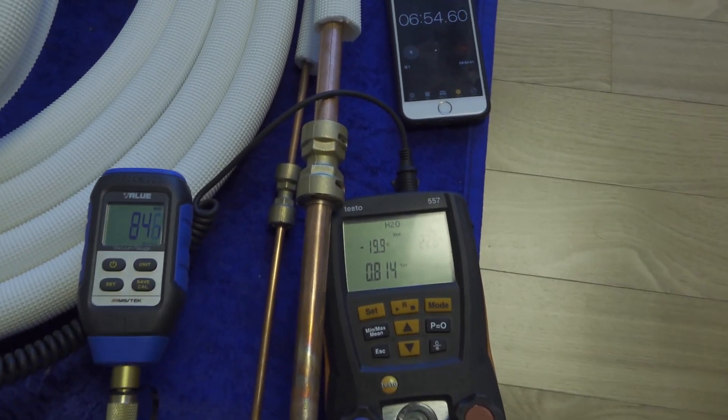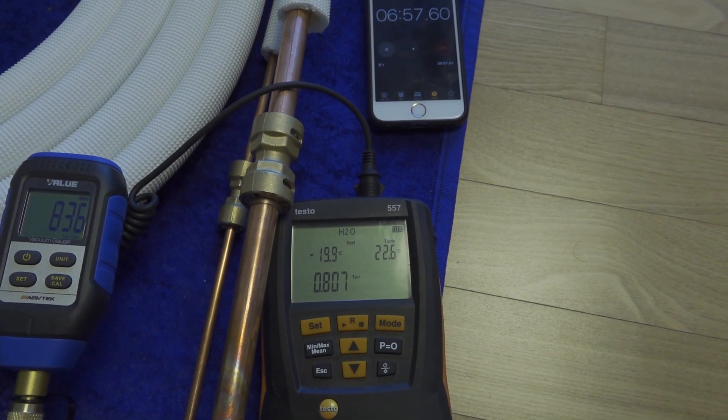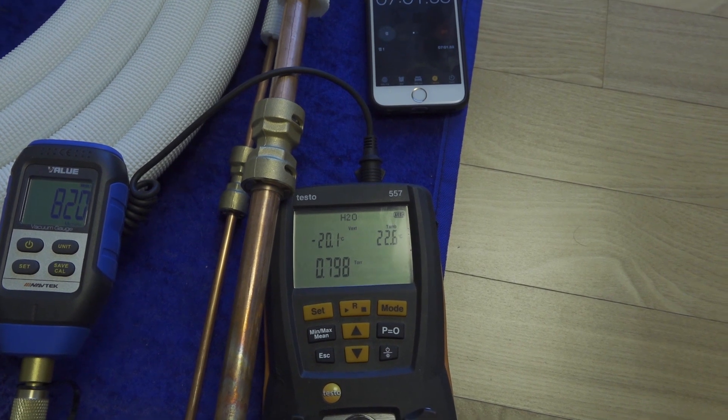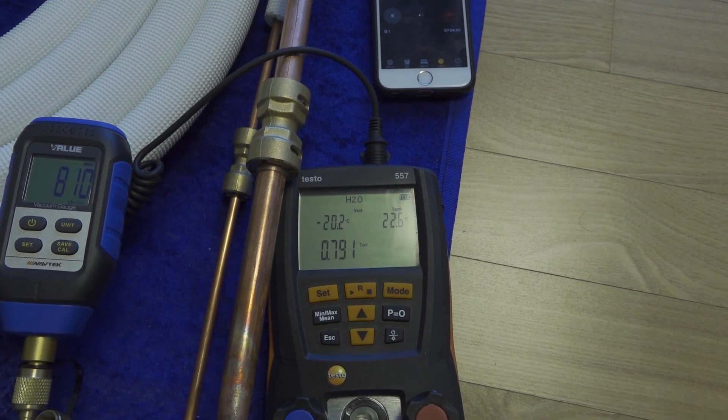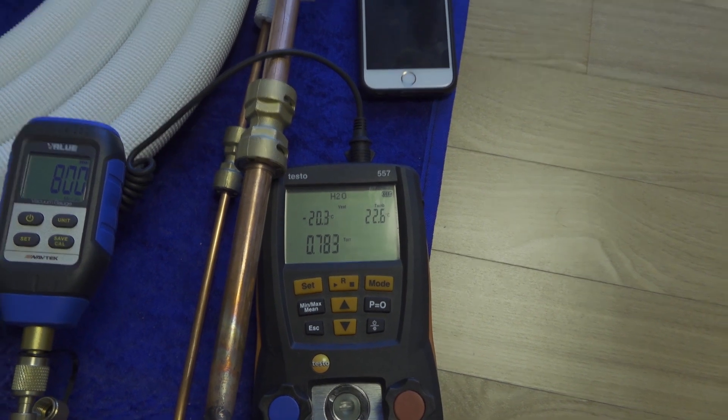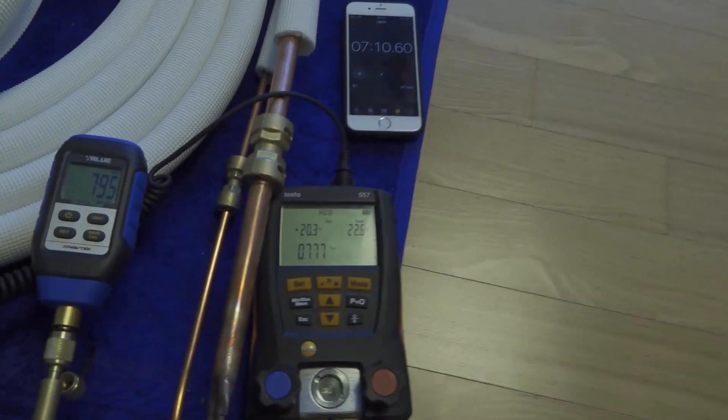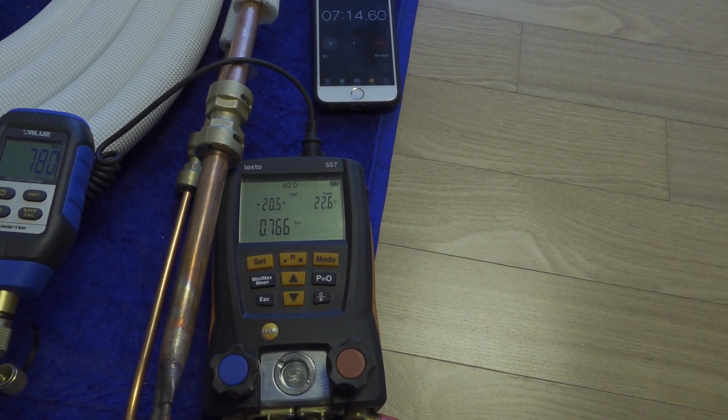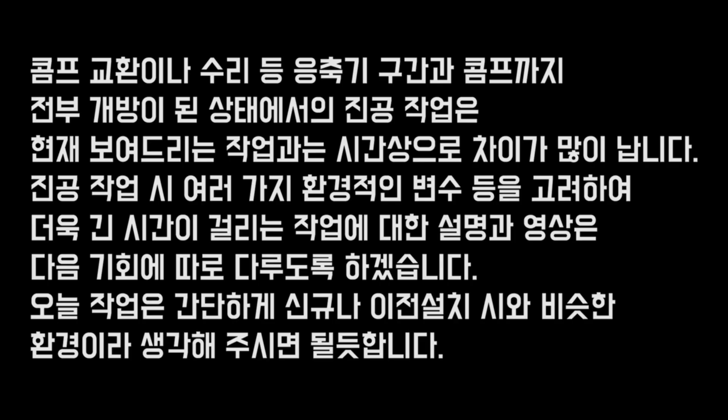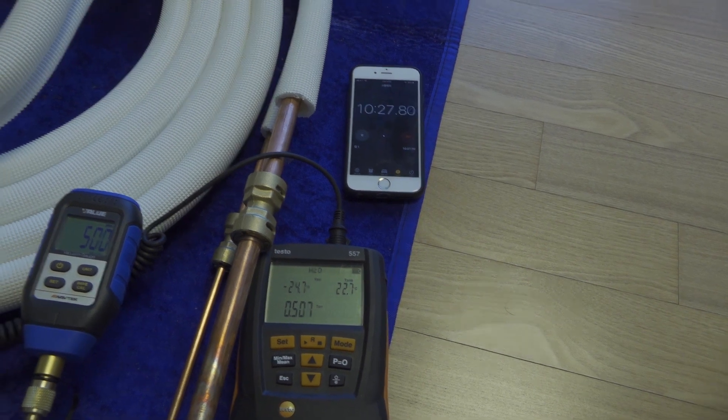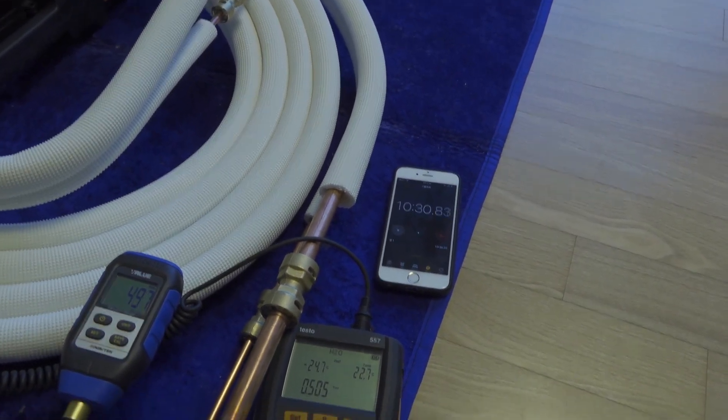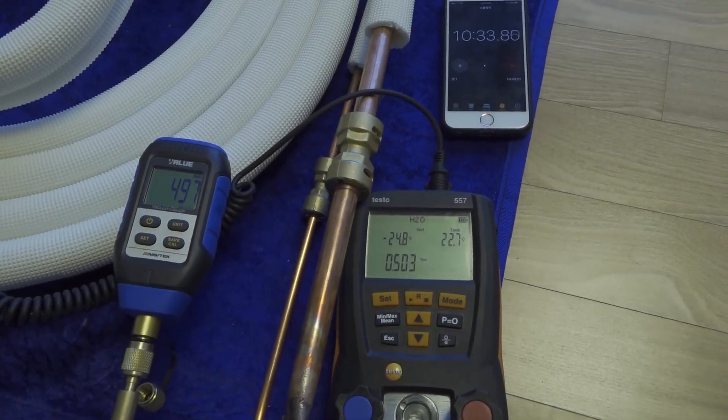In this setup, we're actually pulling vacuum excluding any evaporator or condenser. Usually when we pull vacuum on new piping, we do it with the condenser excluded, so only the evaporator side is open. It doesn't take that long to reach 0.5 Torr with about 5 meters.